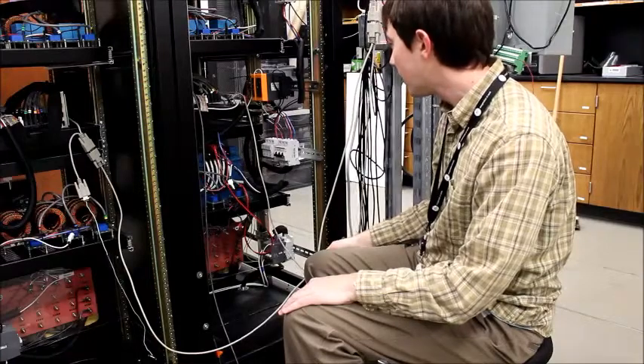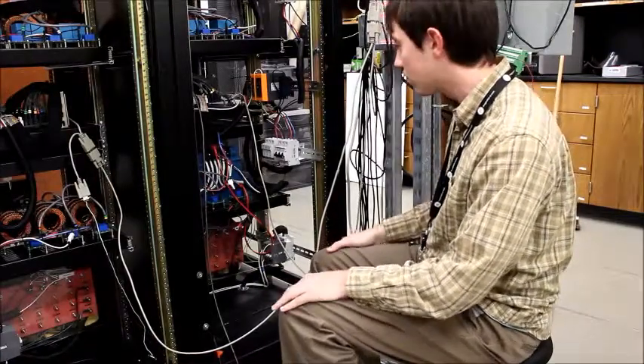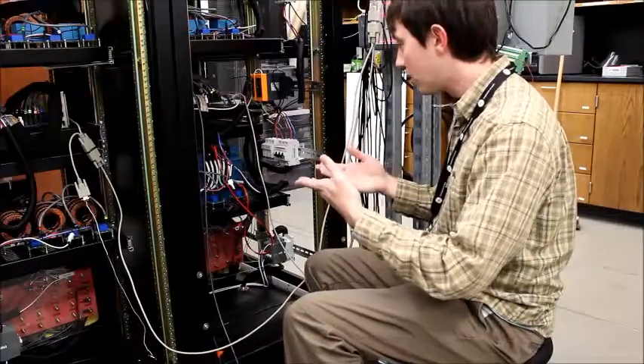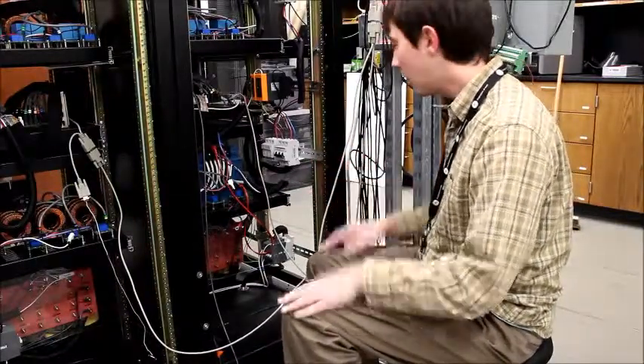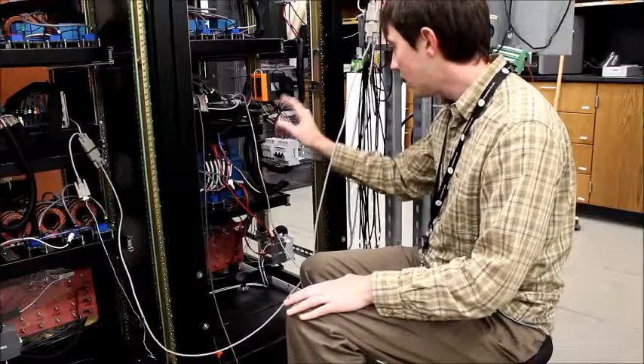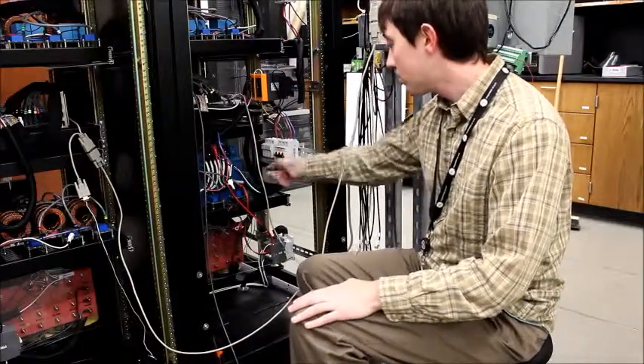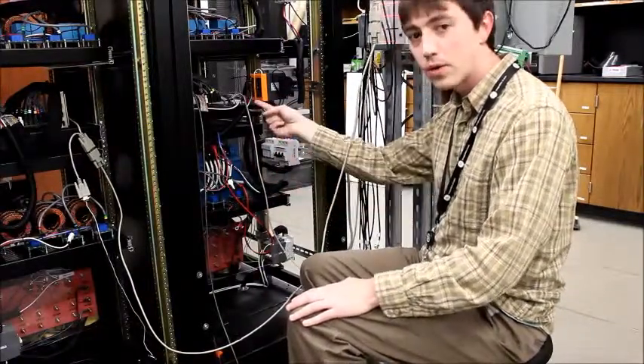by itself without anything else energized, which could cause a problem if all of the switches came on during a reprogram. We wouldn't want that to happen, so just de-energize all the converters, but with the contactor you can still program the DSP.